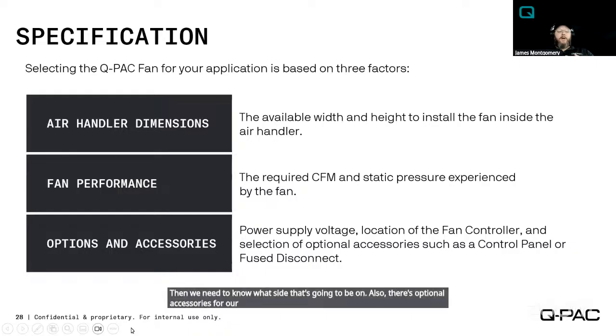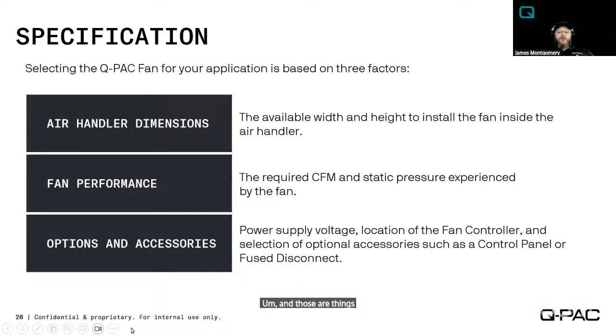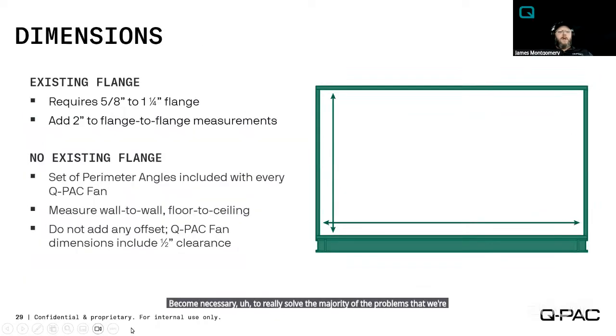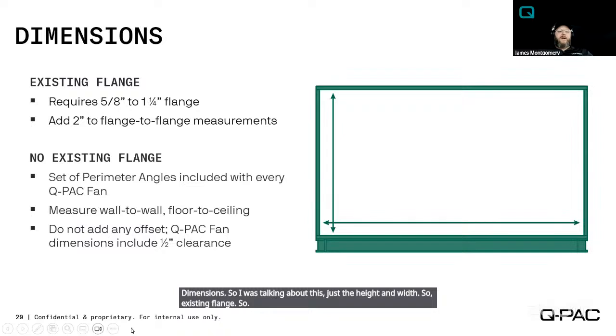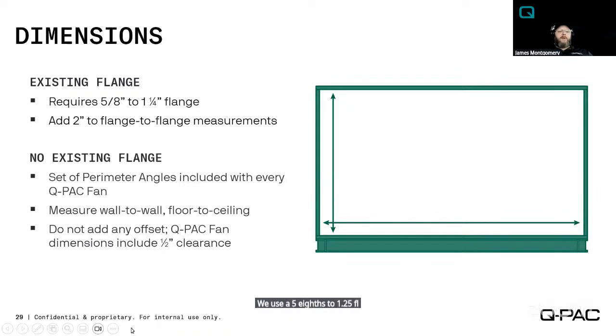Also, there are optional accessories for our system. So we've got a control panel. It's external. It's a fuse disconnect. Touch screens, physical panels, and stuff like that become necessary to really solve the majority of the problems that we're solving now. Dimensions. I was talking about this, just the height and width. So, existing flange: we use a 5/8 to 1 1/4 flange, and we can add a 2-inch flange to flange measurements. If there's no existing flange, a set of perimeter angles is necessary.